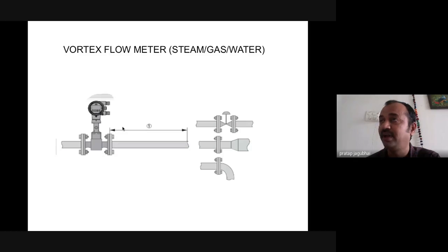The orifice type has inaccuracy because with low flow it is very difficult to get the pressure difference, so it is not applicable for low flow applications, but the vortex has very high accuracy even in the case of low flow. So it has very good turndown as well as very good response, with accurate measurement for saturated steam applications and at 20 degrees superheat also. And for gas and water, this is the best solution for measurement.